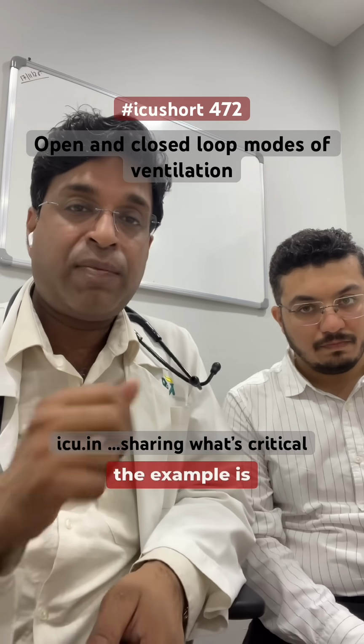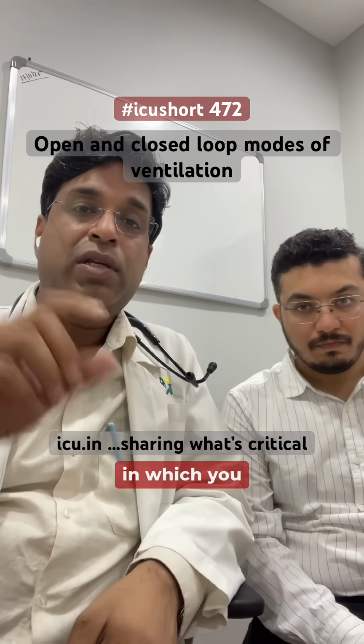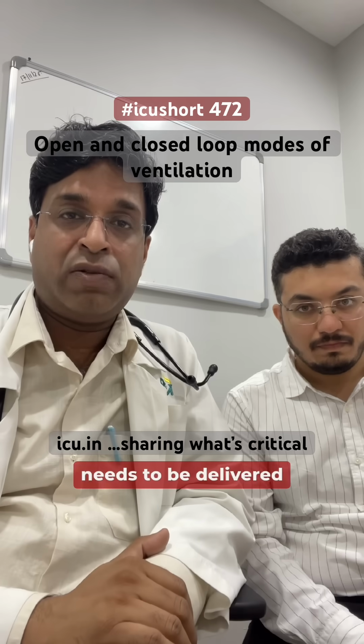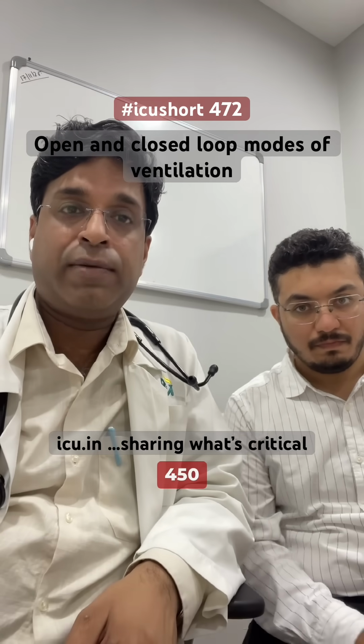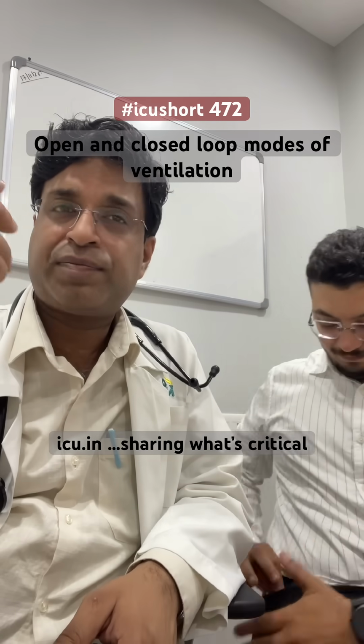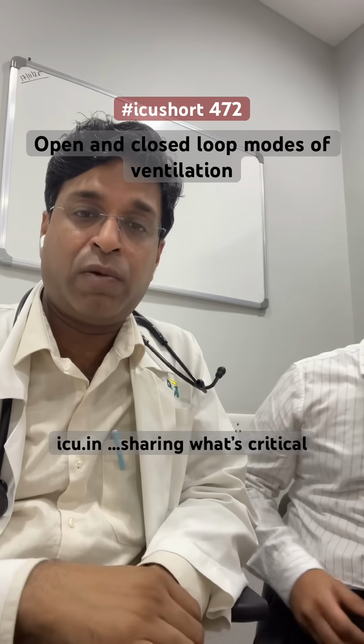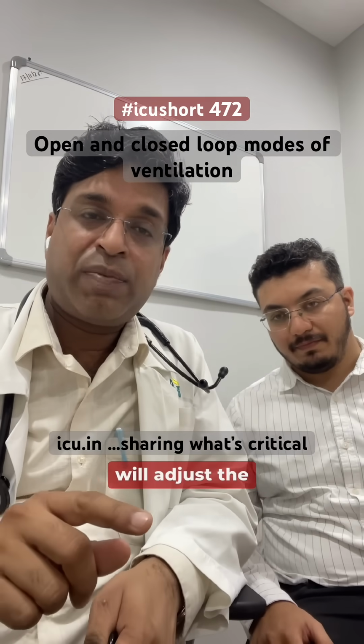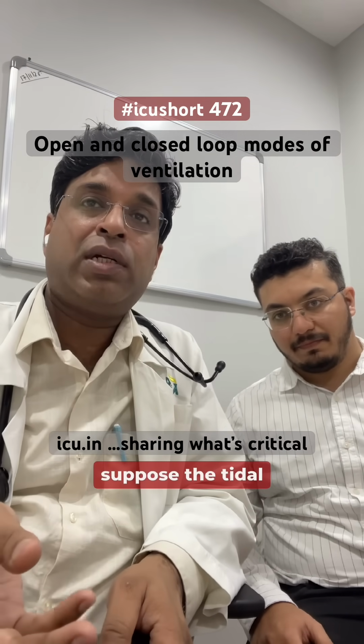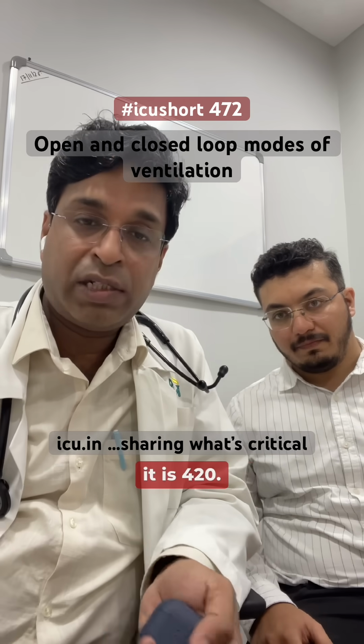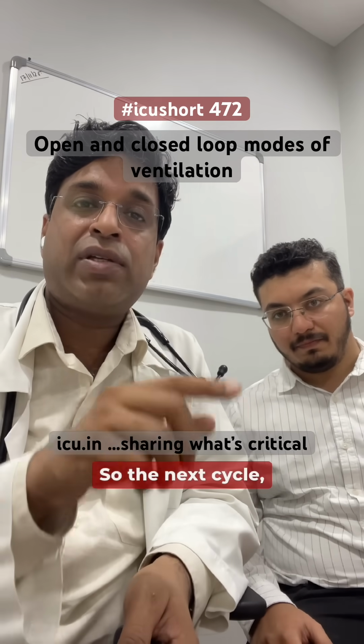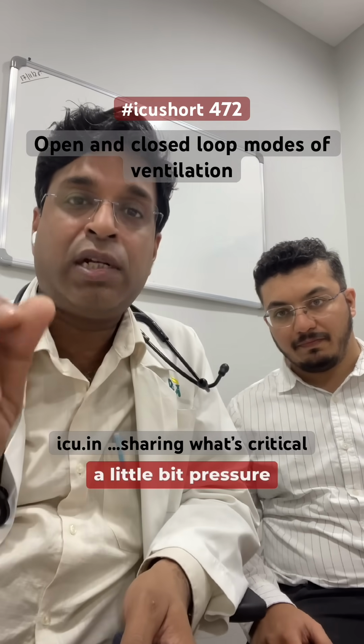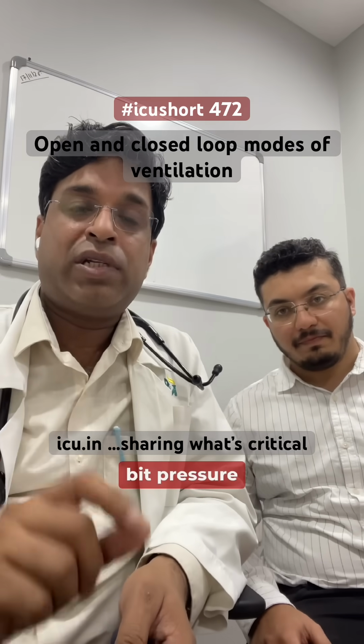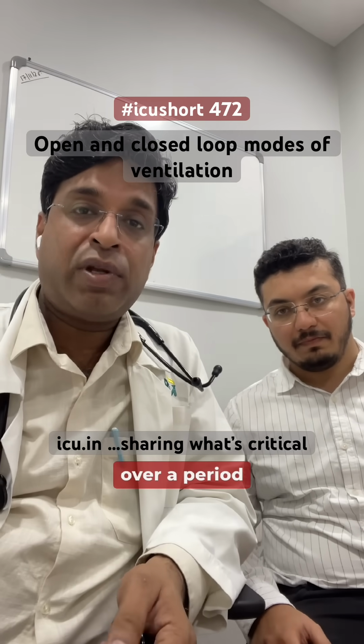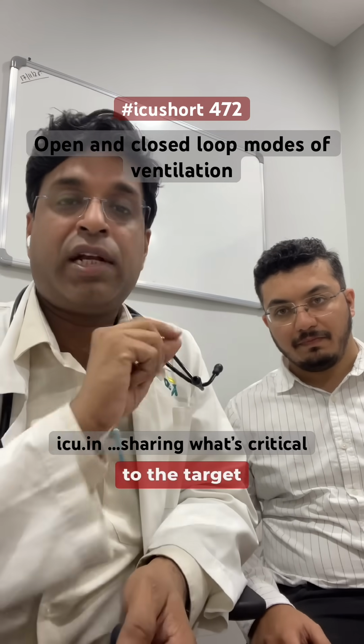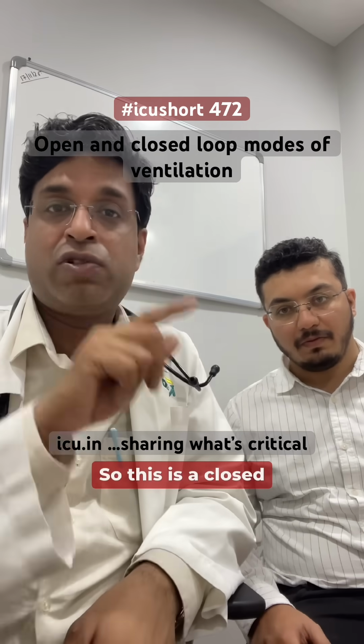In closed loop, the example is volume support mode, in which you decide the tidal volume which needs to be delivered, like we decide 450 tidal volume. So the ventilator will adjust the pressure: suppose the tidal volume at 12 centimeter is 420. In the next cycle, the ventilator will increase the pressure a little bit, then a little bit more, so that the actual tidal volume over a period of breaths is delivered according to the target which we have set. So this is a closed loop ventilator.